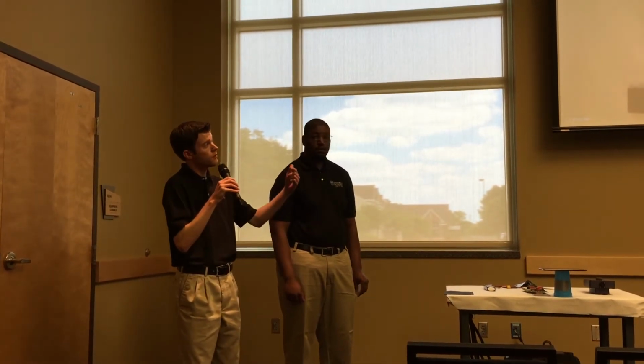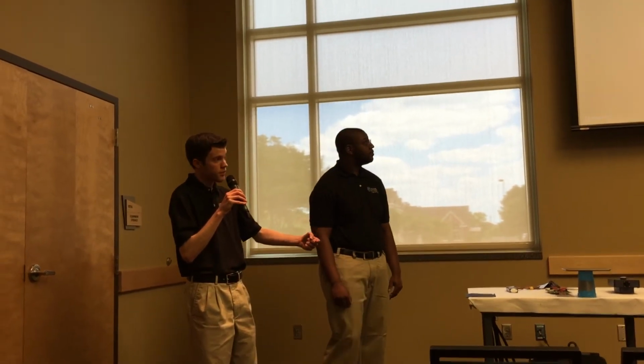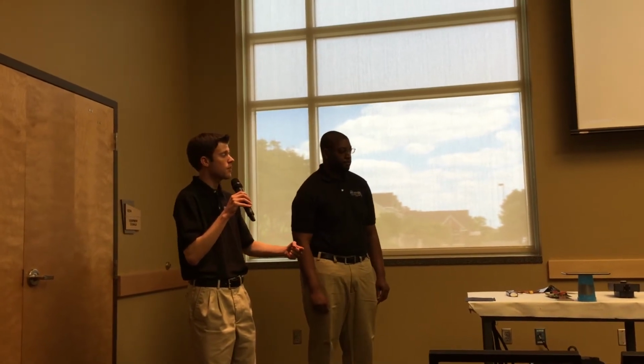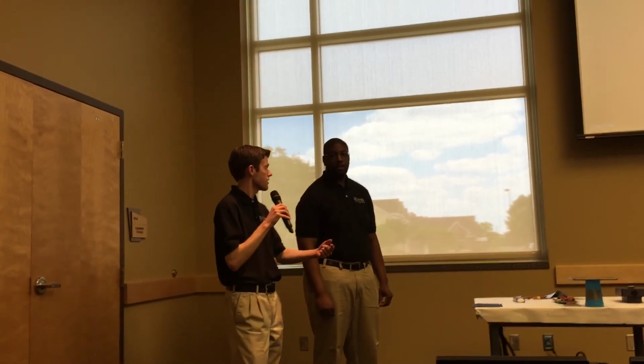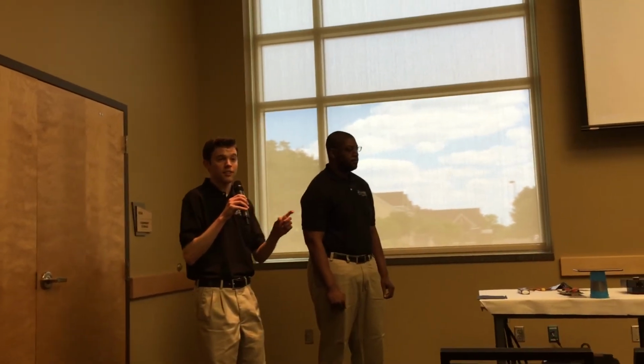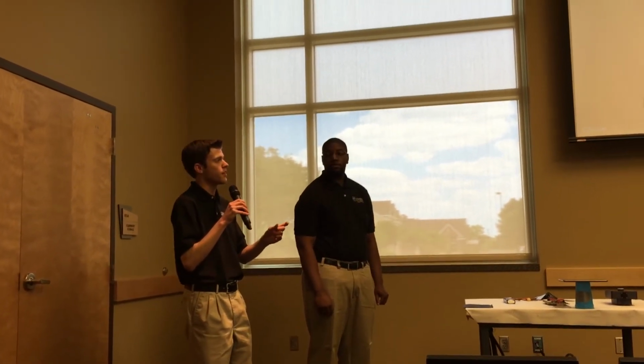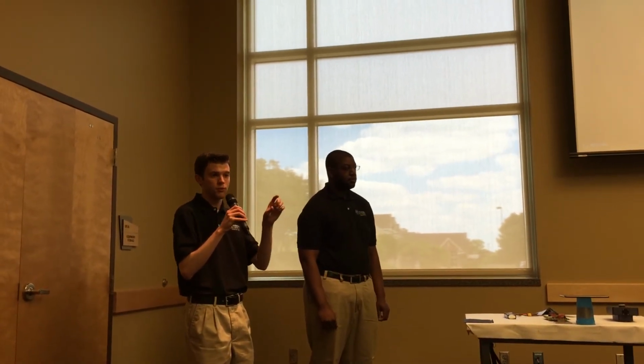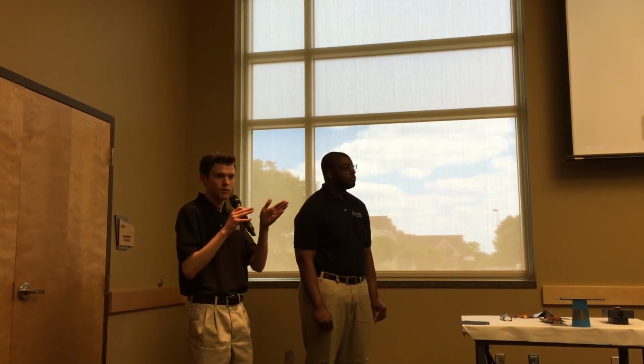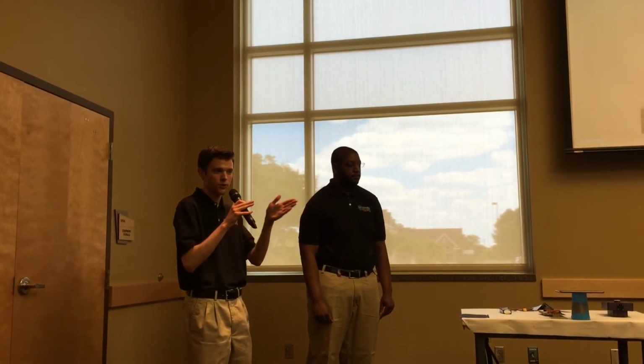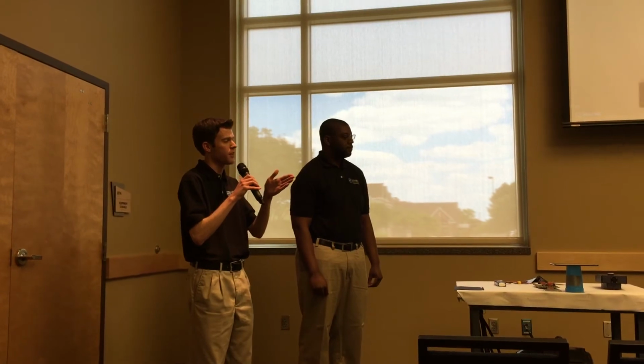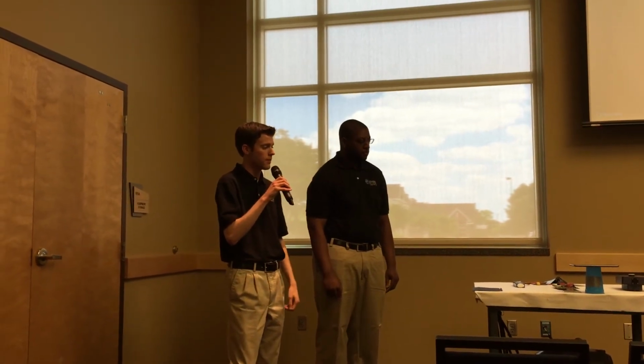After it finishes the resistance imbalance test, it moves on to the inductance imbalance test, in which it applies an AC voltage across the coil and watches the peaks of the resulting signals, looking at the phase difference between the current and voltage peaks in order to calculate inductance on each of the coils.